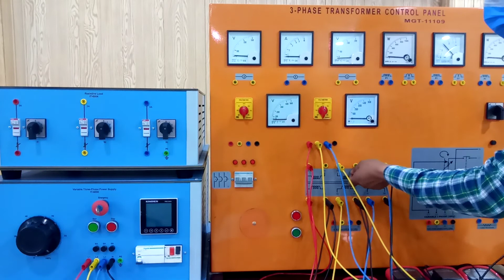Now, as I told you, or as I did on the primary side where the star point was made, similarly we have to make the star point on the secondary side as well. So for that purpose, I will connect the other sides, or you can say the neutral of all the transformers, together.